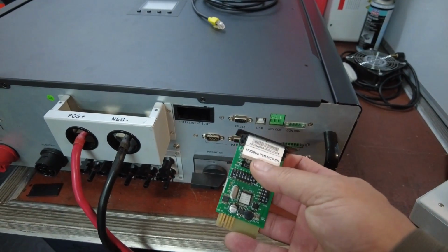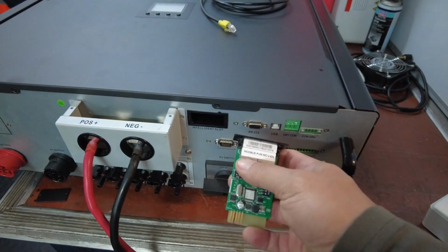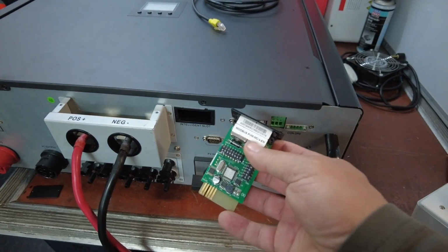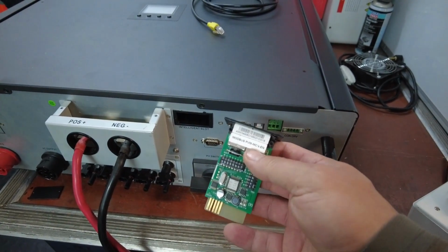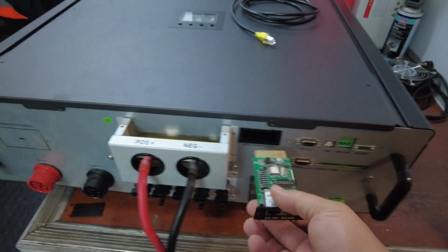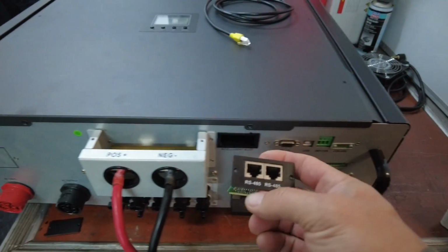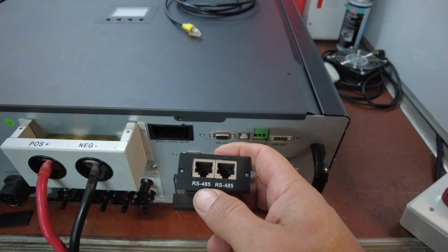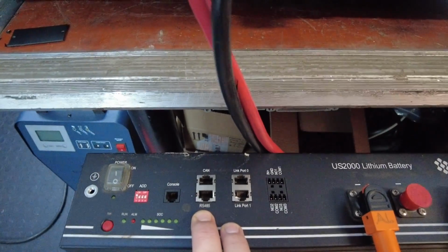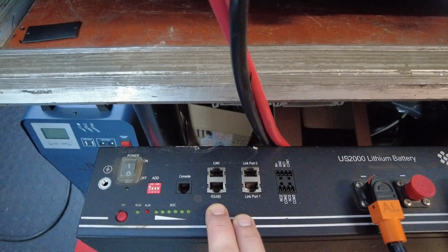Referring to that intelligent slot, you need to get your hands on one of these Modbus cards, which will slot in there, providing you with your RS-485 protocol, which will then assist you in communicating with the battery's RS-485.